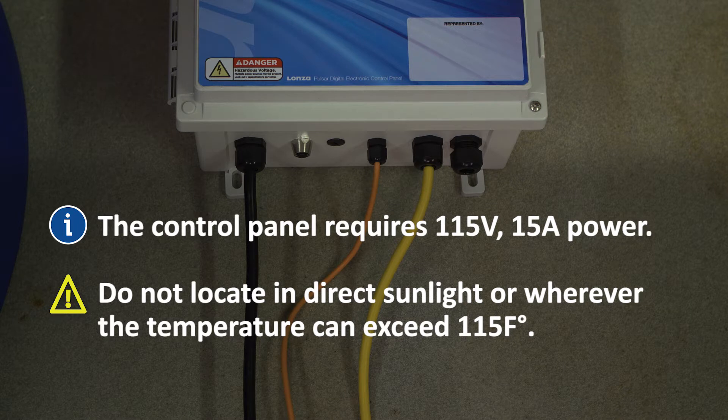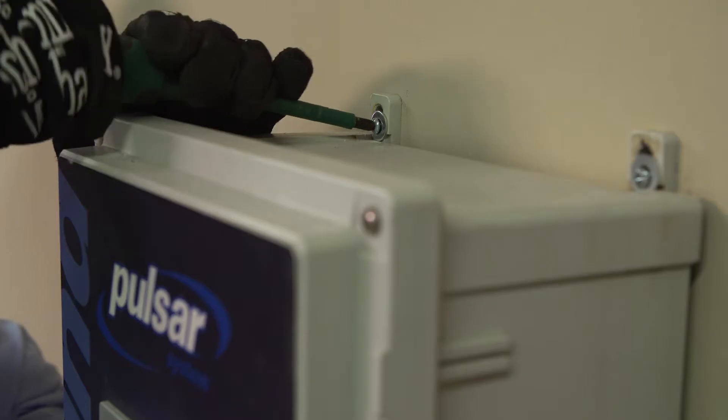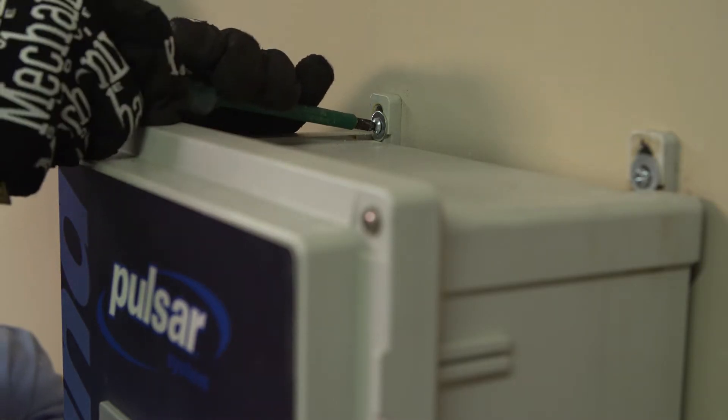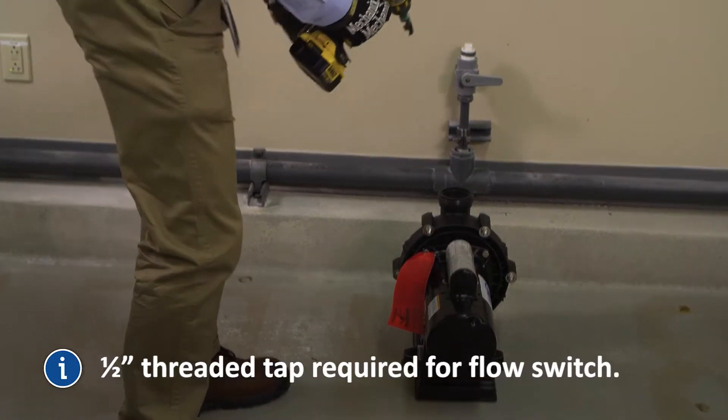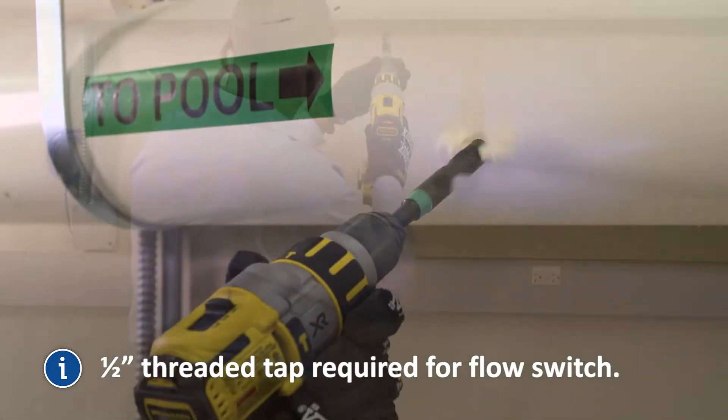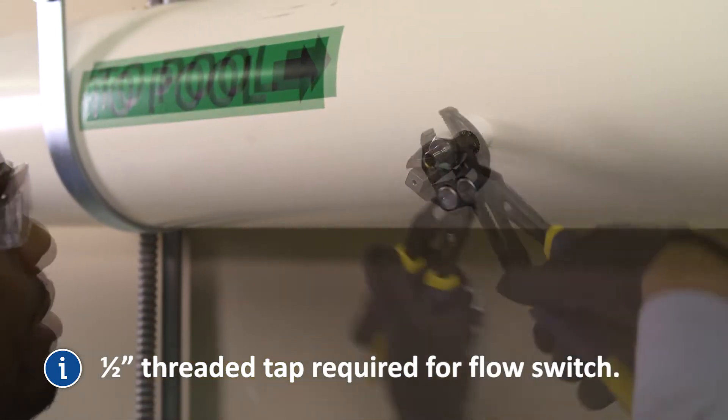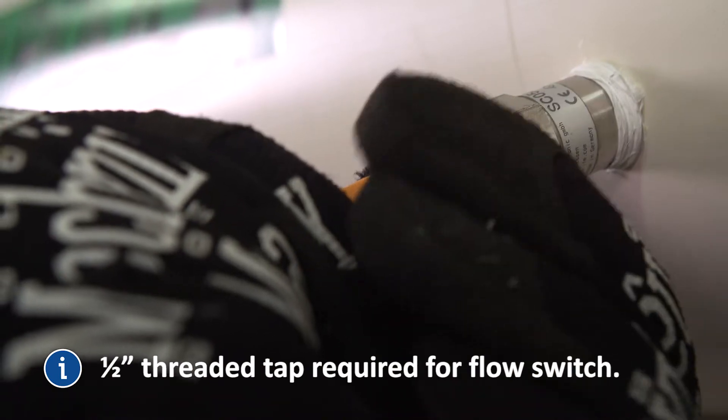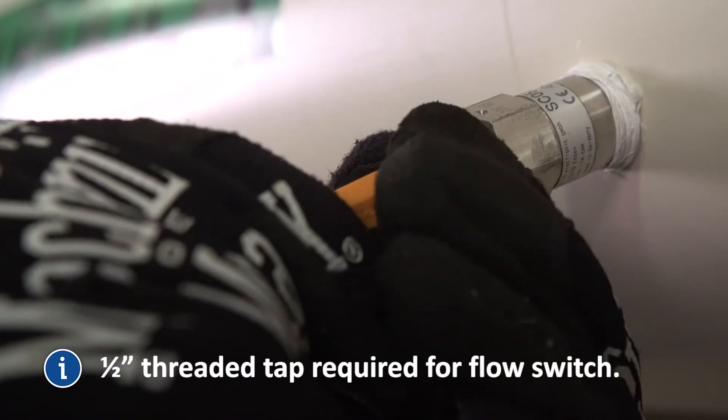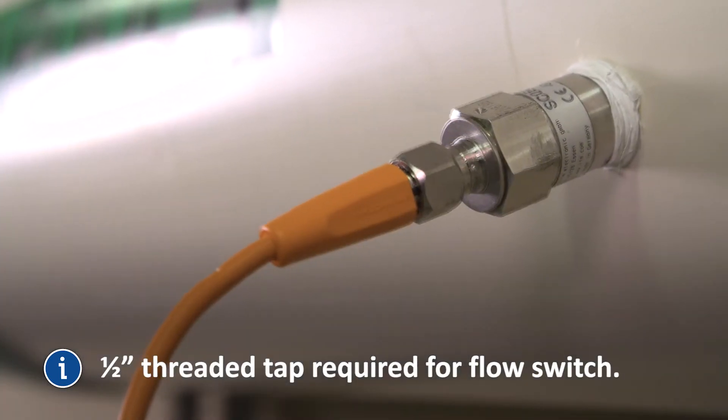Do not locate your control panel in direct sunlight or wherever the temperature can exceed 115 degrees Fahrenheit. Mount the control panel. Install the flow switch in the pool return line near the inlet to the booster pump loop. Then connect the orange flow switch cable from the control panel to the flow switch. This interlocks the booster pump with the pool return water flow to protect the booster pump internals from a no-flow condition.